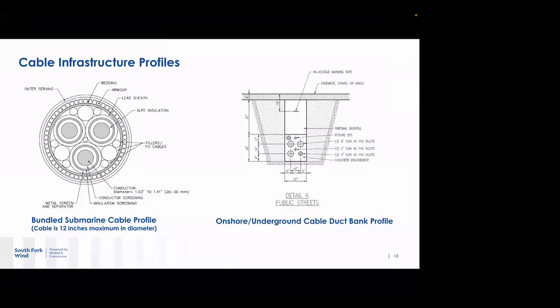The other thing you can see here is the configuration of the cables, both onshore and offshore. Let's look at the left-hand figure, showing the bundled submarine cable with three individual conductors. Magnetic fields, unlike many other things we measure in the environment, like levels of oxygen or CO2, have not only a magnitude but a direction. Each conductor is a source of magnetic fields, but when you place them very close together, the magnetic fields coming towards each other can partially cancel out the field from the other cables.